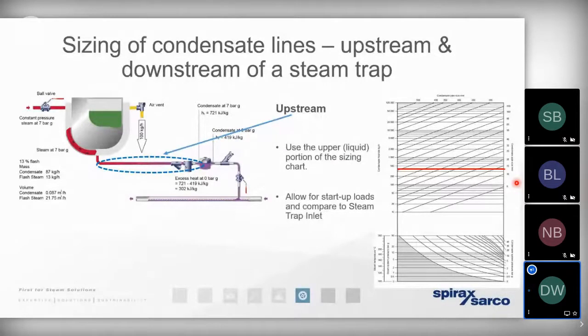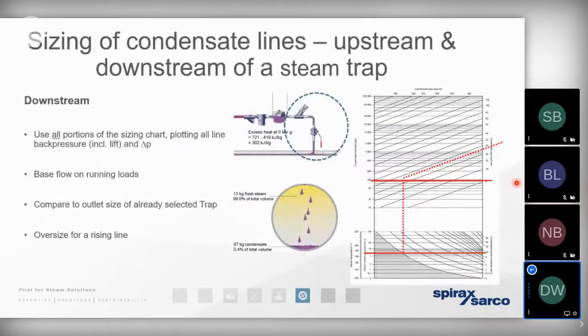Now, the problem that catches out so many engineers, and the vast majority of problems that we encounter on a condensate distribution system, is trying to understand what actually happens when that condensate falls in pressure across the steam trap. Remember, we need that fall in pressure because we need to allow for the motive energy in the steam to push the condensate across the trap and energize it so it can travel back to the boiler house where it can be reused. The thing to bear in mind is if we've got high pressure, high temperature condensate with that high amount of sensible heat energy contained within it upstream of the steam trap, when we get that fall in pressure downstream of the steam trap, we know that the fall in pressure means the condensate has got to fall in temperature and it's got to give up some sensible heat.